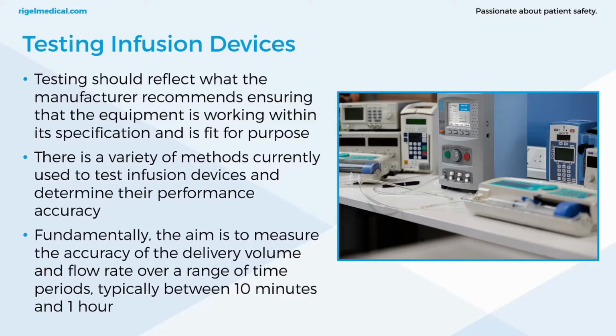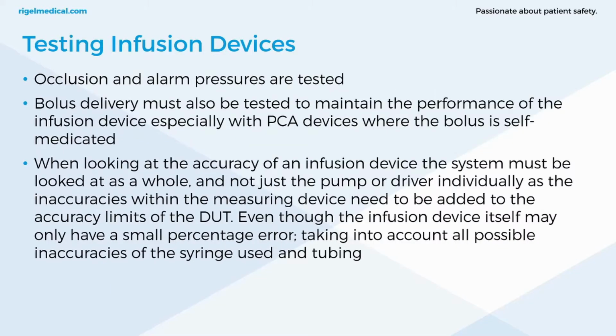So fundamentally the aim is to measure the accuracy of the delivery volume and flow rate over a range of time periods, typically between 10 minutes and 1 hour. However, within manufacturers, you might see testing up to 24 hours. It does vary, but for regular testing, testing in biomedical departments and hospitals, you're typically looking at 10 minutes to 1 hour. Basically, occlusion and alarm pressures are also to be tested. Bolus delivery must also be tested to maintain the performance of an infusion device, especially with PCA devices where the bolus is self-medicated by the patient. We'll come on to some of these characteristics from bolus and occlusion.